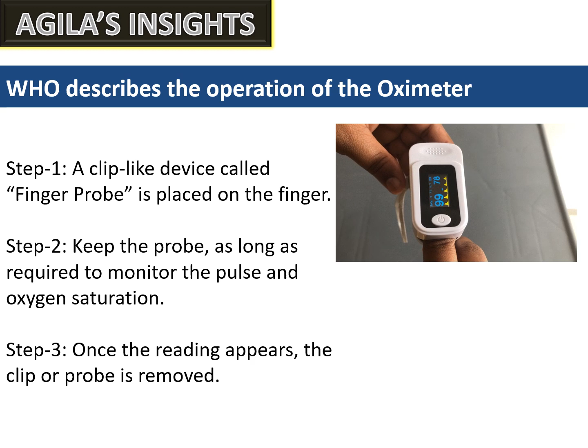Care should be taken when using the pulse oximeter. So there are a number of points to keep in mind. Avoid movements during the measurement. If measurement is through fingers, make sure you remove nail polish or henna since it may interrupt the measurement. The color can absorb light emitted by the oximeter and interfere with the detection of oxygenated hemoglobin.